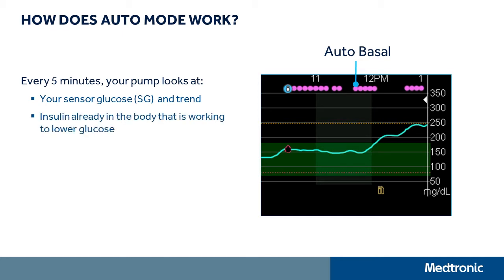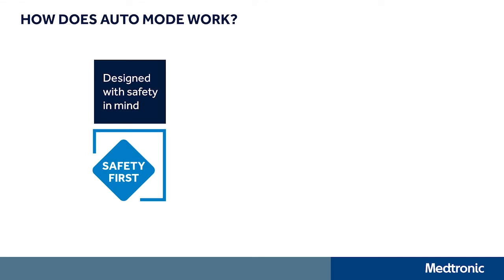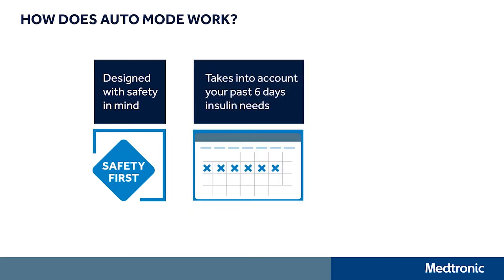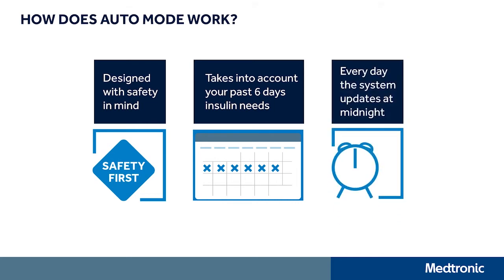The pump also takes into account how much insulin is already in your body still working to lower your glucose. The active insulin you see on your pump screen is the bolus portion. Every 5 minutes, these factors are taken into consideration. Auto mode was designed with safety in mind. It takes into account your past 6 days of insulin needs, and it also adapts every day at midnight. The goal is to safely maximize your time spent in target range while preventing lows from the over-delivery of insulin.